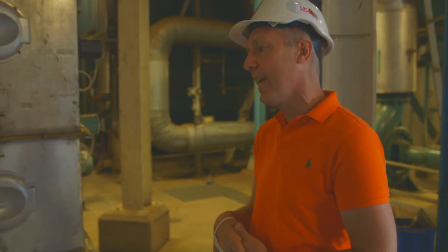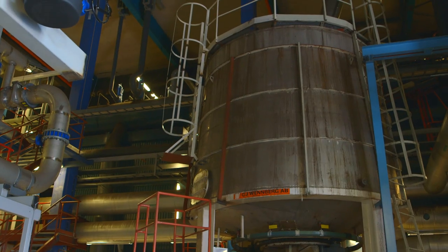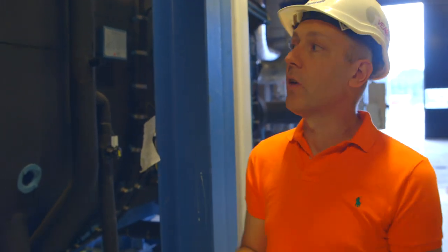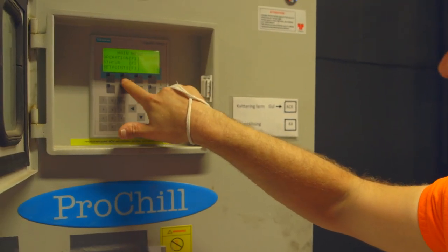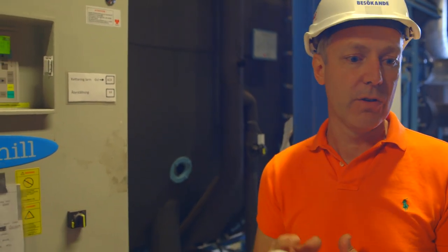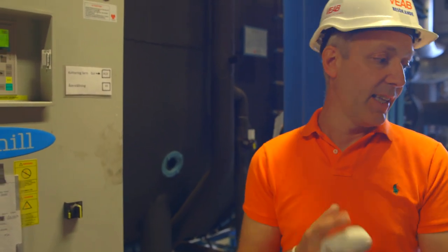The first step away from oil was made in 1980, when the old oil boiler was modified to become a highly efficient bio boiler. Here we can see that the chiller is set at 5.8 degrees — that is what we deliver to the network. As we have cables in the ground and under the sea, we have to set it at a lower temperature to ensure that our customers get cold water at 6 degrees.